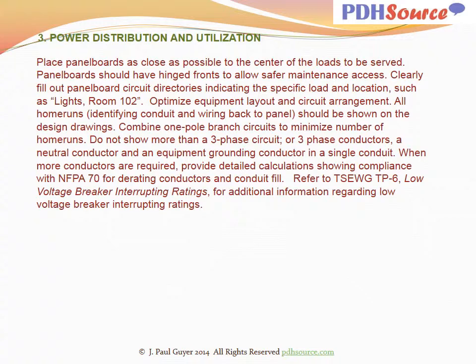Place panel boards as close as possible to the center of the loads to be served. Panel boards should have hinged fronts to allow safer maintenance access. Clearly fill out panel board circuit directories indicating the specific load and location, such as lights, room 102. Optimize equipment layout and circuit arrangement. All home runs, identifying conduit and wiring back to panel, should be shown on the design drawings. Combine one pole branch circuits to minimize number of home runs.